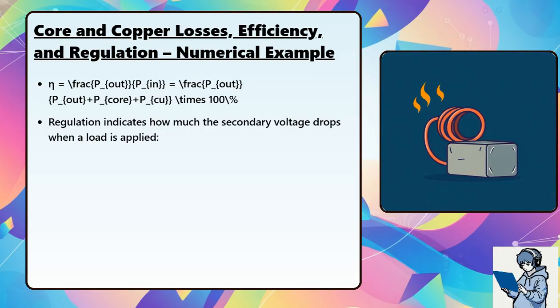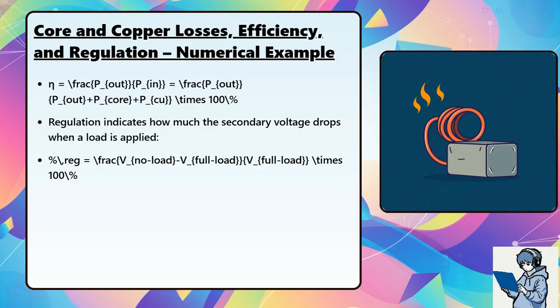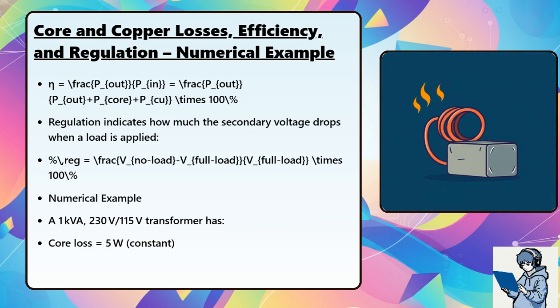Regulation indicates how much the secondary voltage drops when a load is applied. Percent regulation equals the difference of V no load minus V full load divided by V full load times 100%. Numerical example. A 1 kilovolt ampere, 230 volt over 115 volt transformer has core loss equals 5 watts constant.